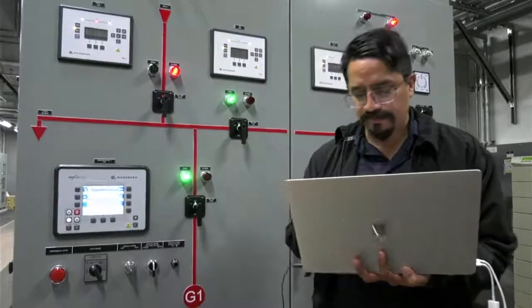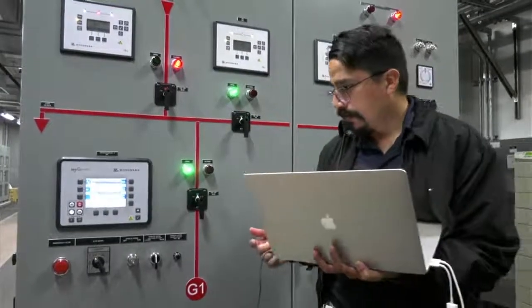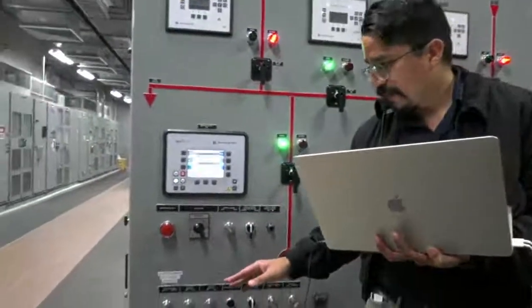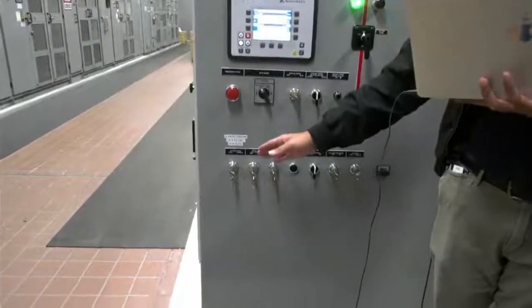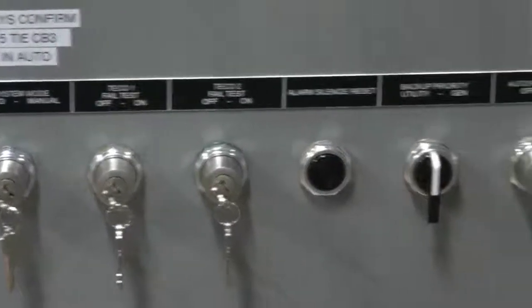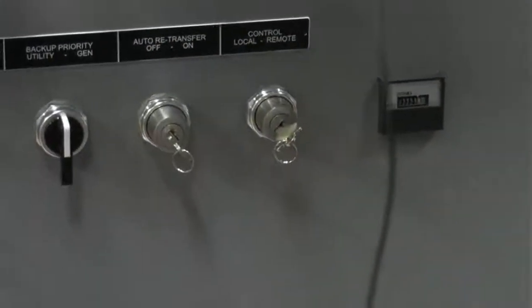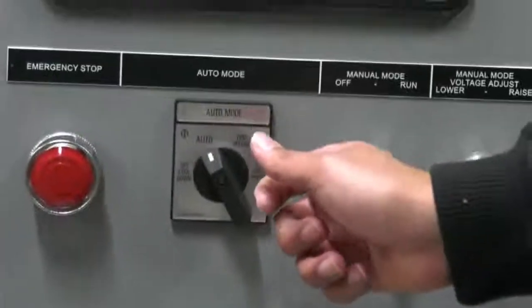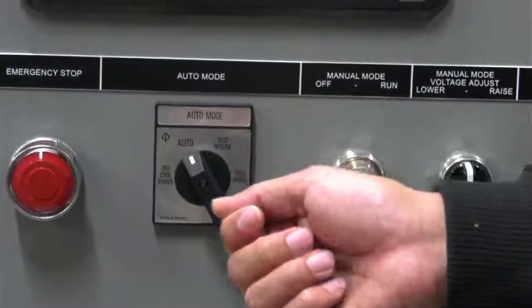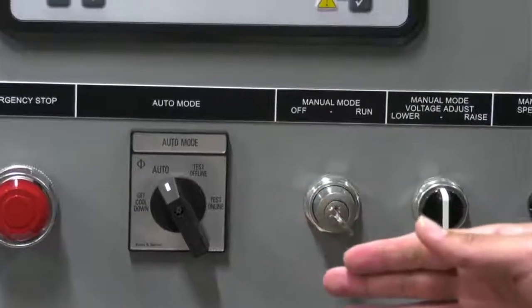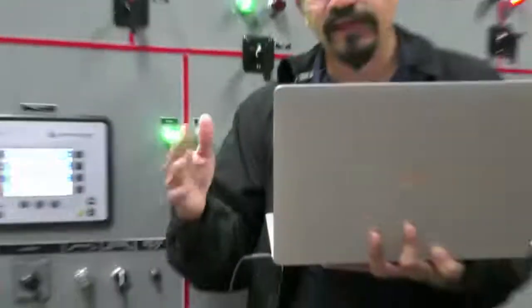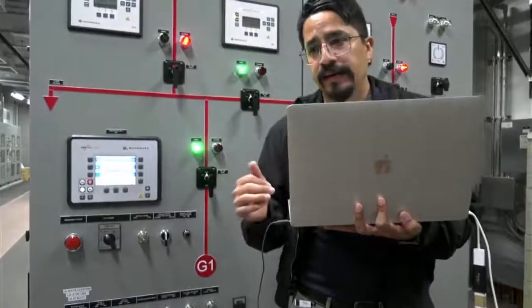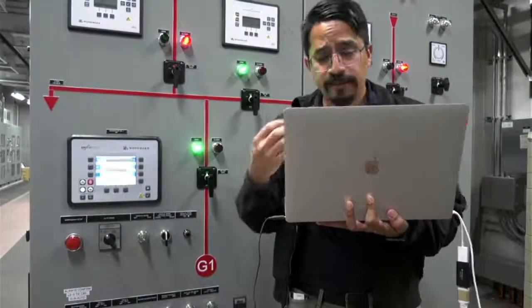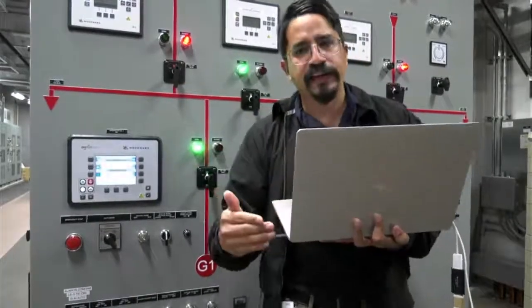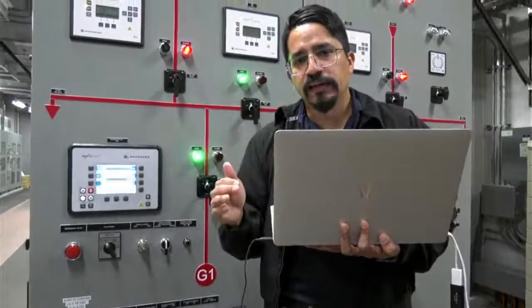That's online. To do the offline, you follow the same procedures. You go with the system in auto, you confirm you have local control, and you go to the auto mode switch and select test offline. What it does is run the engine without closing the circuit breaker. So it's going to just run the engine and leave it running at rated speed and rated voltage, so you can confirm the engine is working and everything is ready to be back on.